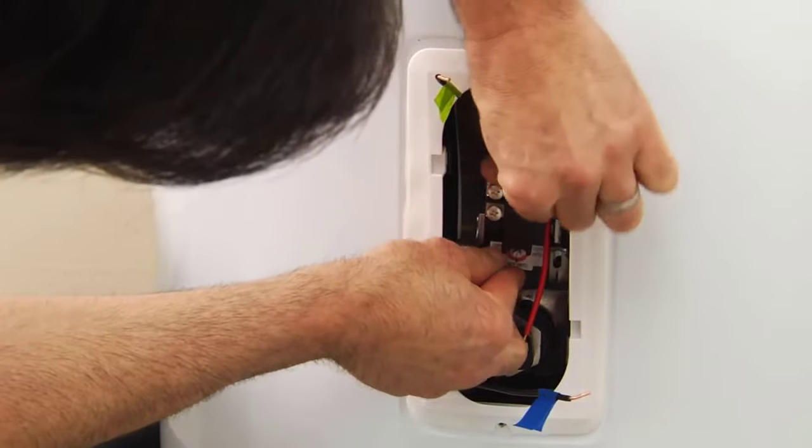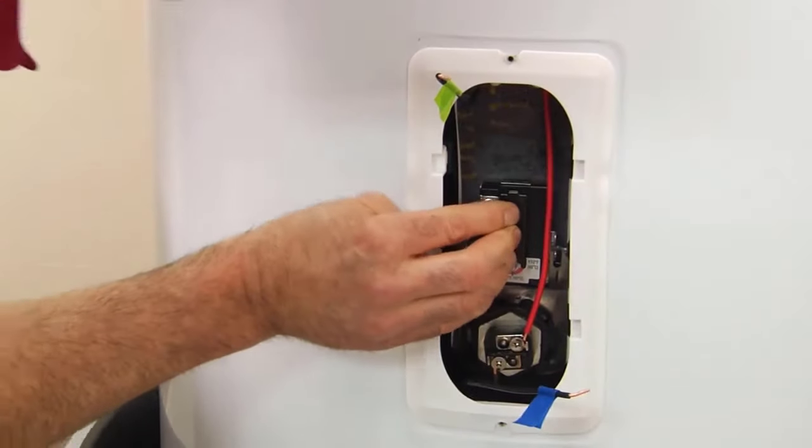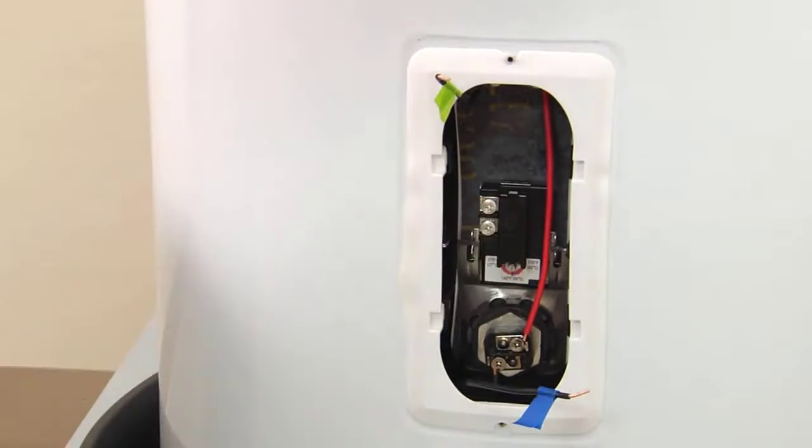Replace the old thermostat with an identical new one. Be sure the back of the thermostat is pressing tightly against the tank because that affects the accuracy of the temperature reading.